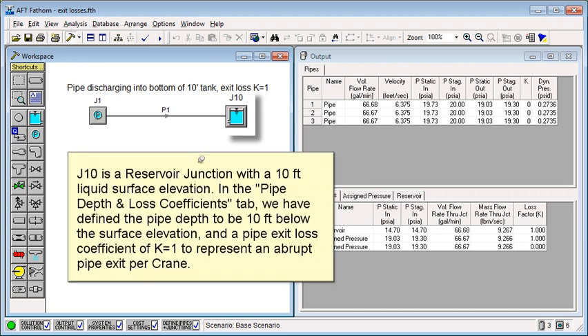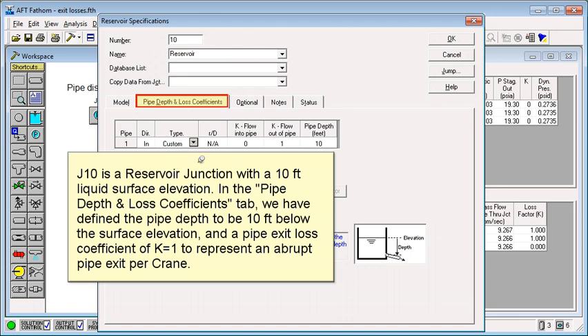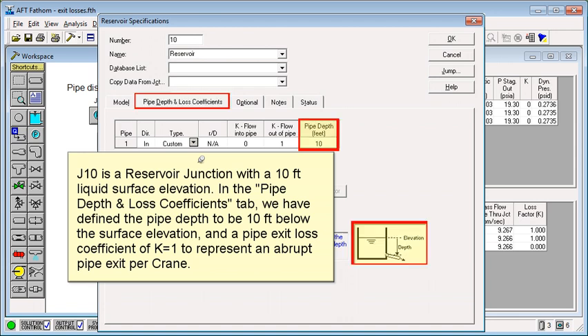J10 is a reservoir junction with a 10 foot liquid surface elevation. In the pipe depth and loss coefficient tab, we have defined the pipe depth to be 10 feet below the surface elevation and a pipe exit loss coefficient of K equals 1 to represent an abrupt pipe exit per Crane.